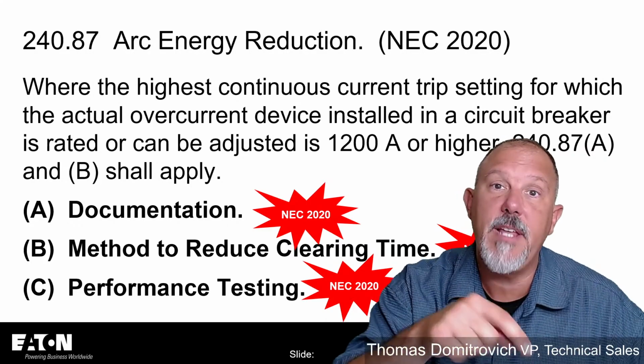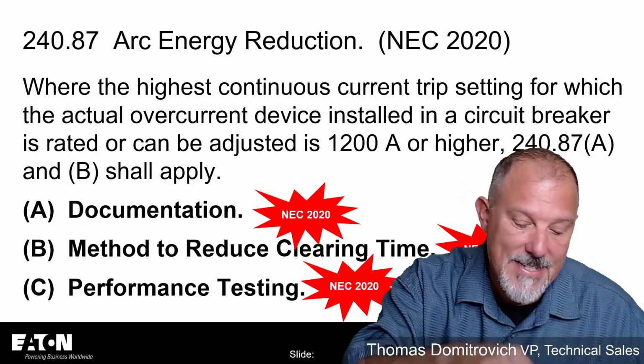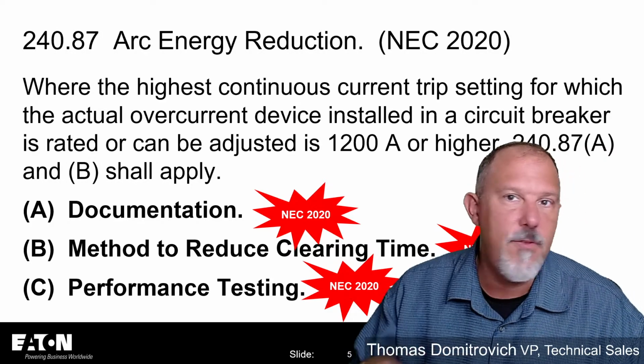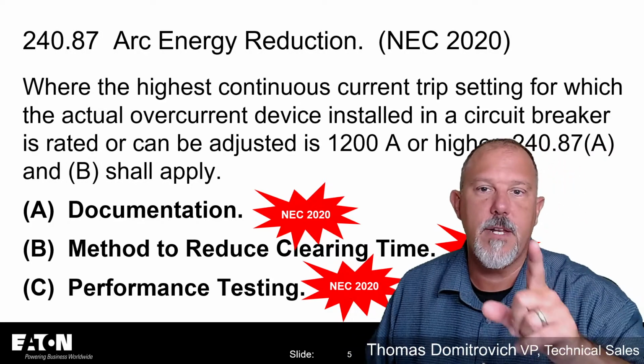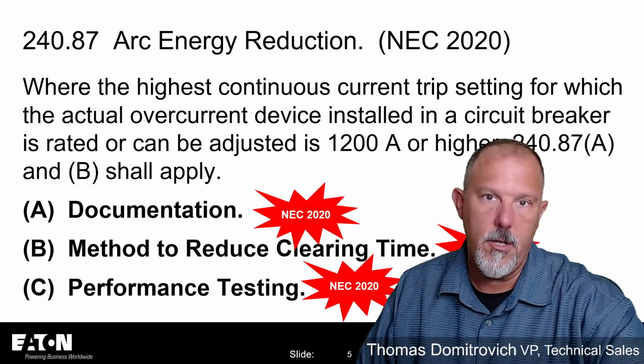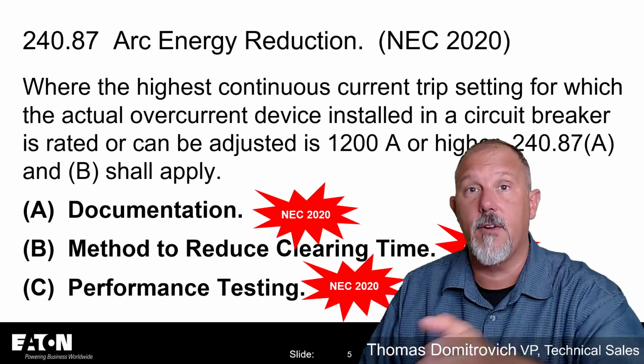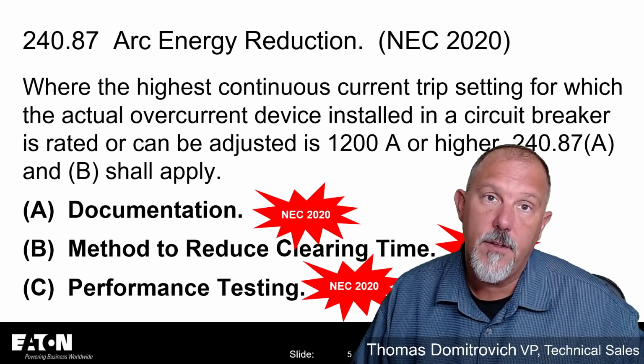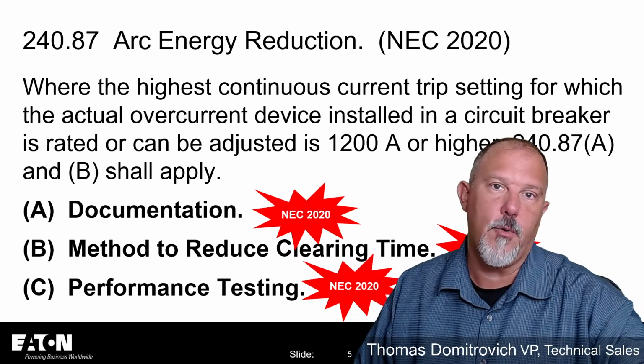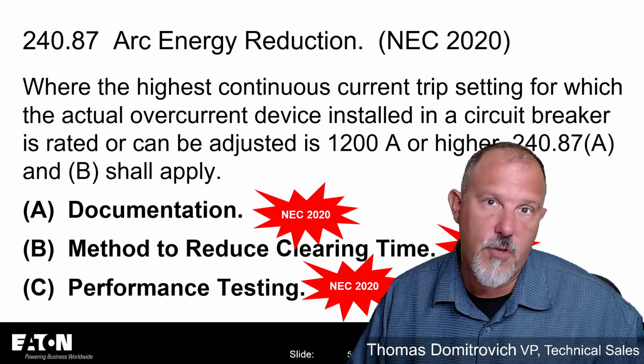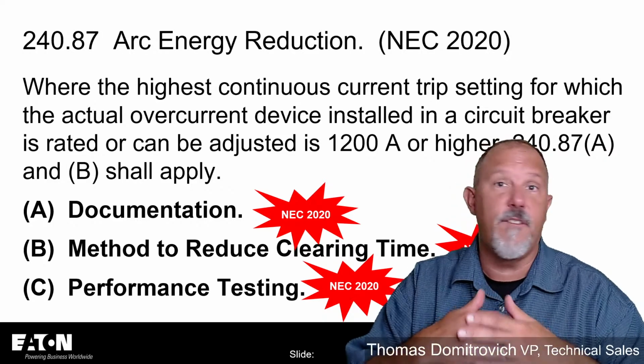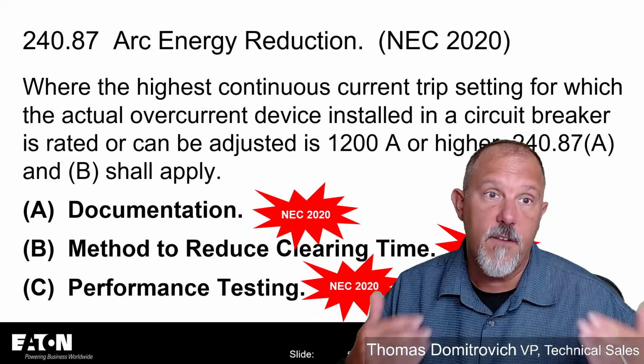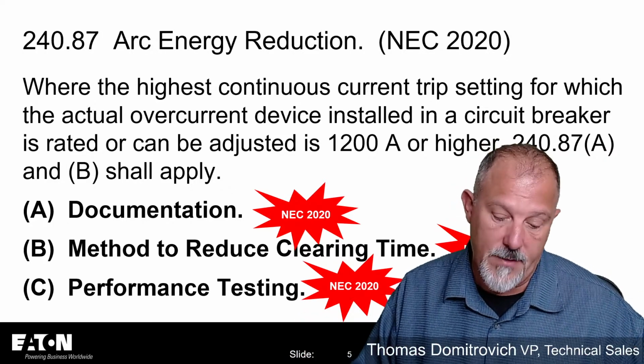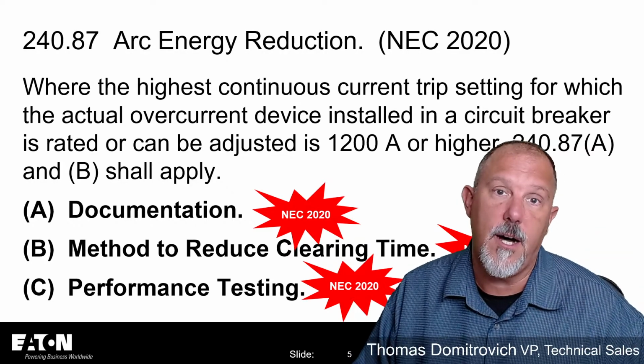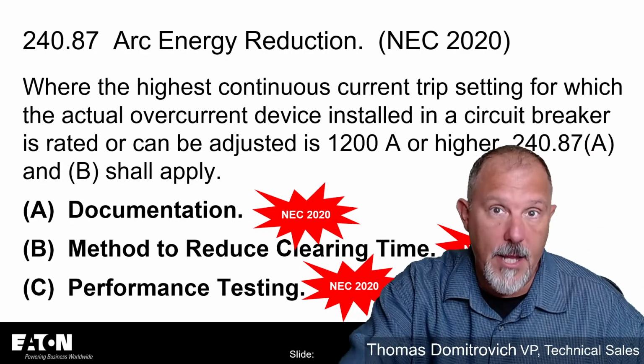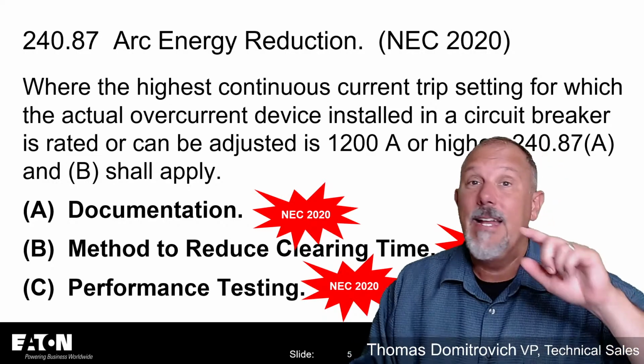So you should be able to identify exactly every place in that drawing where you have a breaker that is 1,200 amps or larger, or can be adjusted to 1,200 amps or larger, so that you know where you're going to have to review the requirements of 240.87. That's the first point of entry for circuit breakers: 240.87 applies when you can adjust it up to 1,200 amps. Now, catch that in plan review.